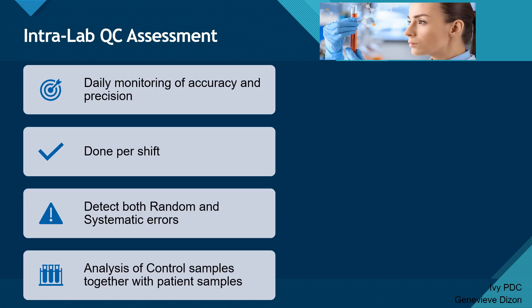The first one is intra-lab QC. Intra-lab is within the laboratory quality control, so these are the things done by the medical technologists in the laboratory. Intra-lab involves the daily monitoring of accuracy and precision. We monitor accuracy by testing control materials, and this is done per shift.